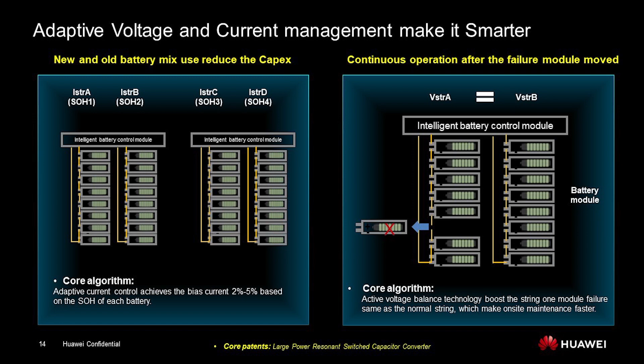And in this way, we find another principle to control the voltage. By the same module, we can boost the voltage so that one less failed module equals the rest of the strings. For example, if this battery module fails, we can move it out and reconnect the string, and this cabinet can keep operating. But in the industry, if there is no voltage boosting, the whole cabinet fails. So it can give us a very long time for the backup to come to site, because lithium-ion batteries cannot be transported by airplane. This is what we call adaptive voltage and current management, and it is also a very core patented technology.